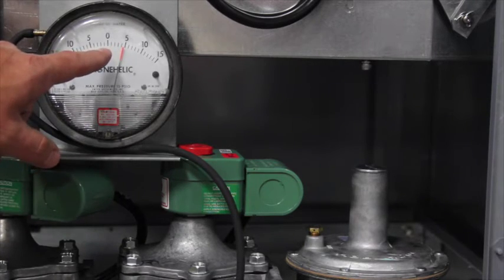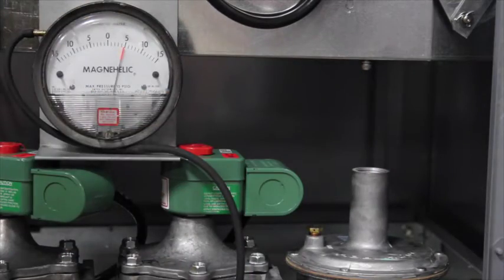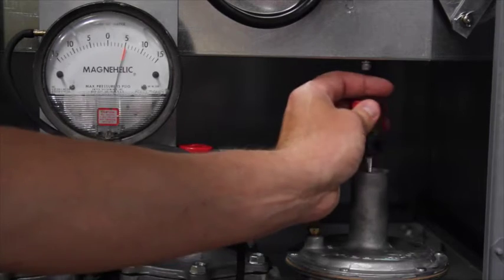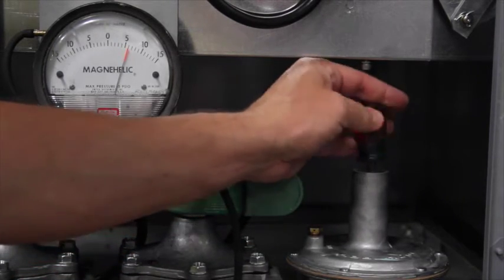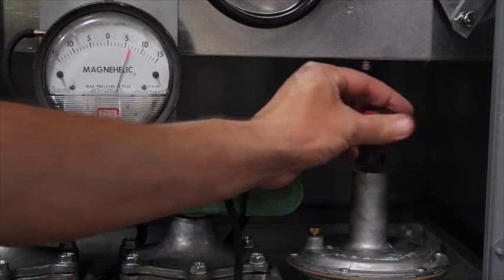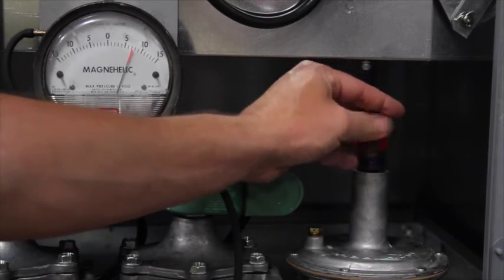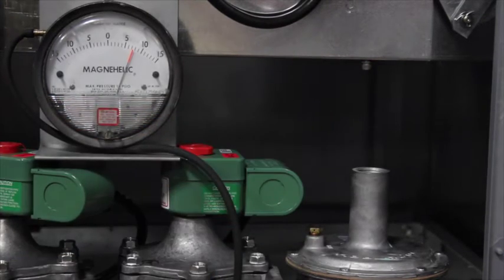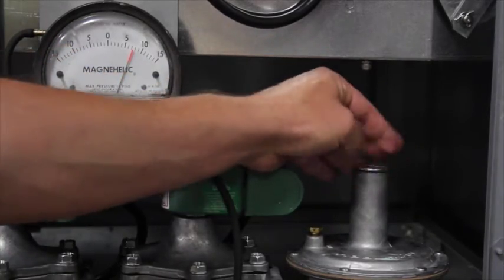Now you must look at the nameplate and adjust the unit regulator to the nameplate manifold differential pressure. Remove the cap on the regulator and turn it clockwise until you reach your nameplate setting. Once you have matched your nameplate setting, reinstall the cap on the regulator.